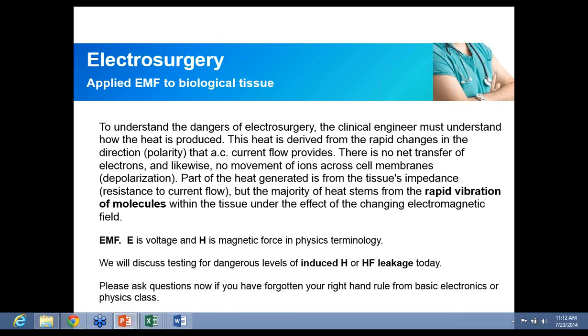An interesting experiment you might want to try is to set up your ESU with a pencil and wrap the hand pencil cord around an 18-inch small fluorescent tube, a completely disconnected fluorescent tube. Connect that pencil to your ESU analyzer and discharge the pencil into your ESU analyzer at even a small amount of wattage, and the fluorescent tube will light up. That's because the H is inducing the particles inside that fluorescent tube. It excites them and lights them up. Though there's no direct electrical contact, that's an induced field that happens. Too bad this is just a webinar and I can't display that.